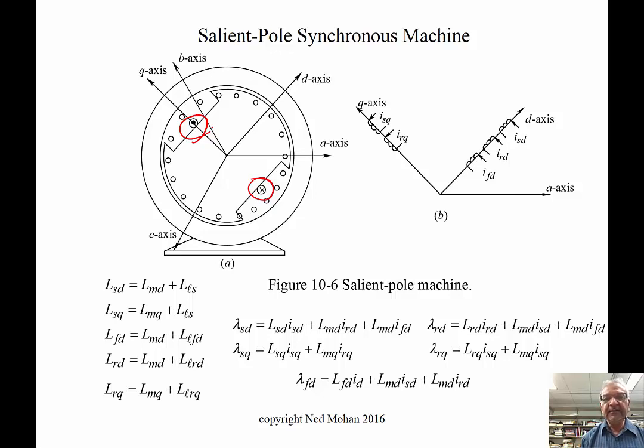The damper winding is just like an induction machine. In the rotor, there's a squirrel cage—bars inserted parallel to the axis of the shaft, short-circuited on both sides. The same thing is done here.